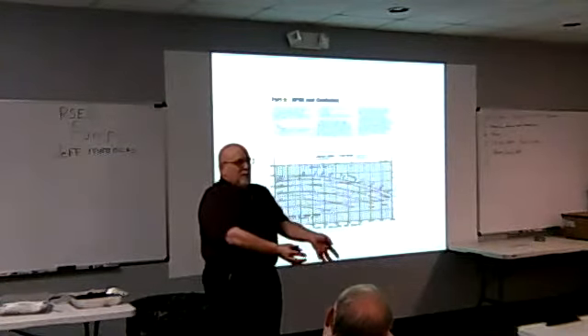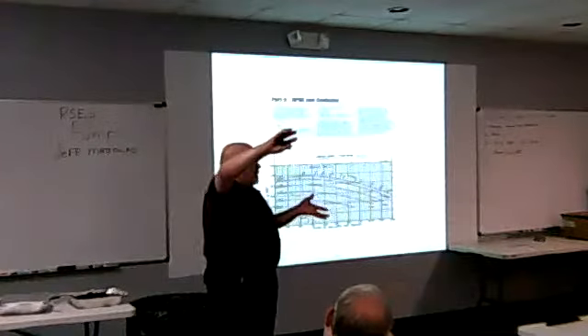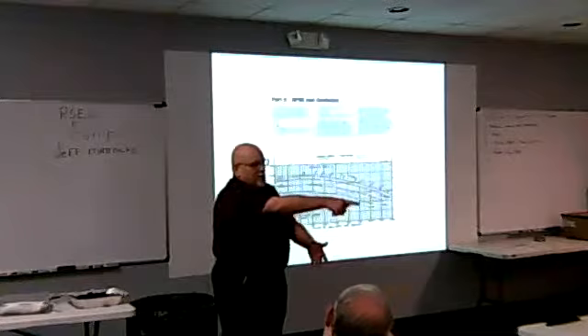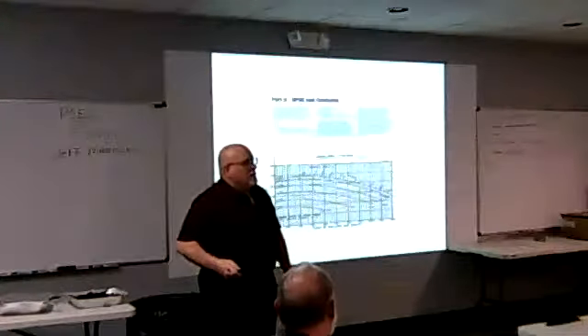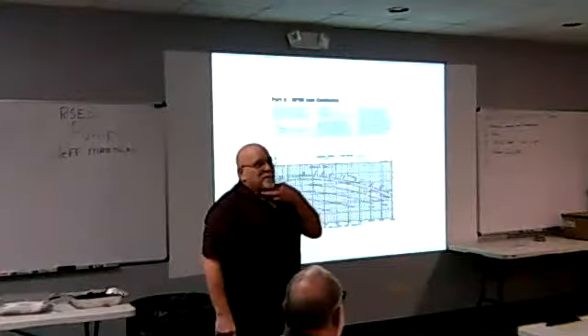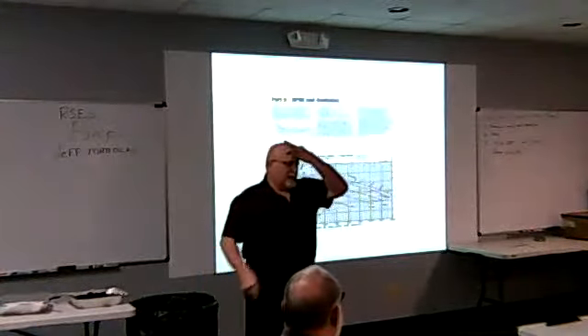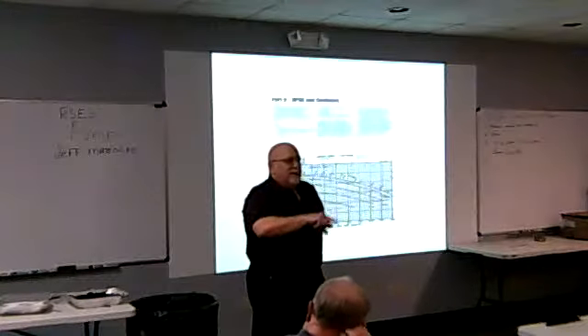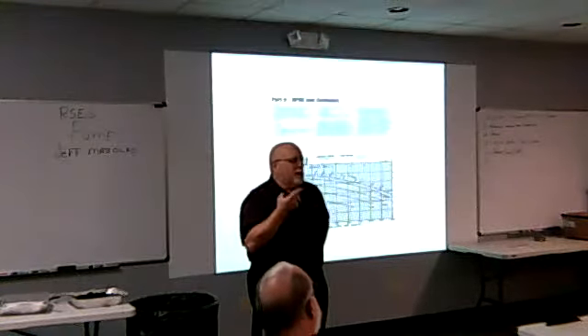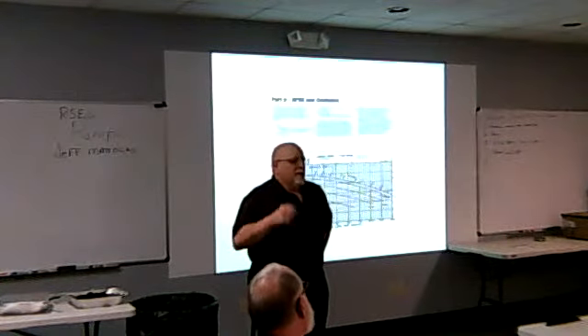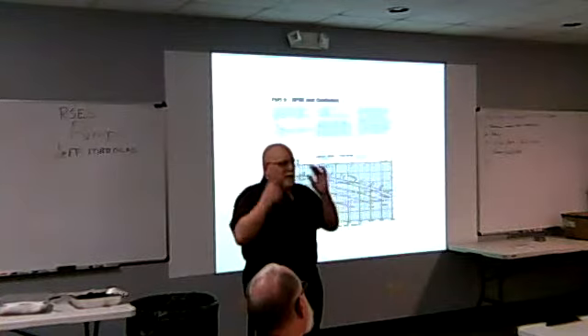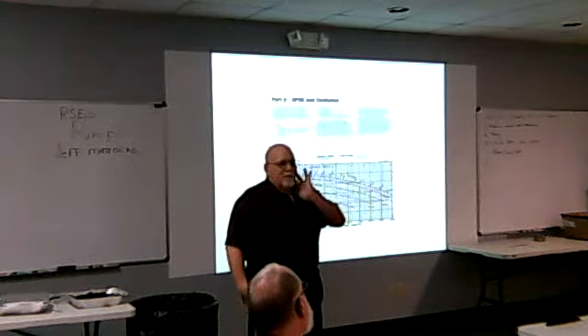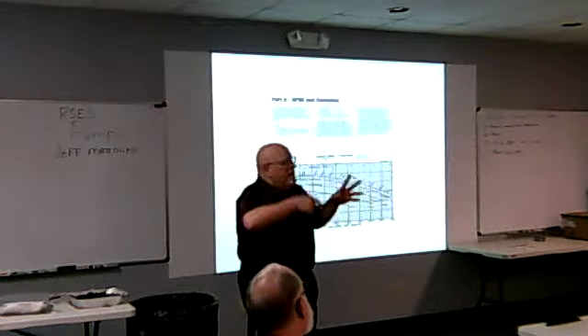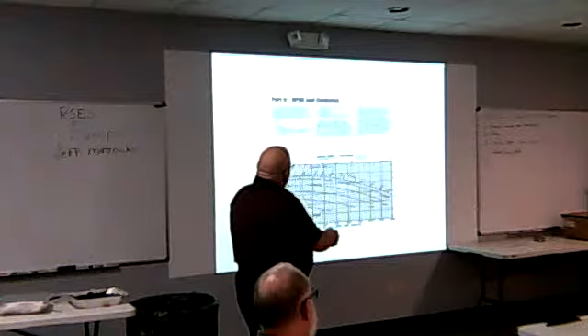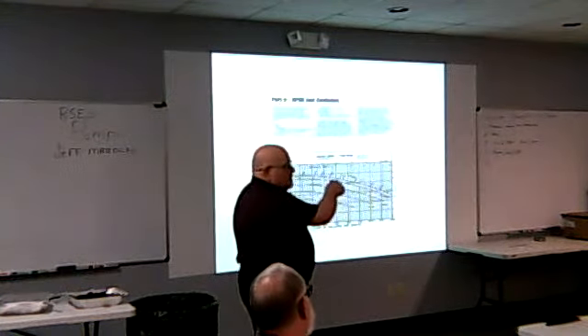And when it boils, there are these little steam bubbles. Now the steam bubbles travel out the vane, hit high pressure, guess what happens to them? They collapse, and they do that. It will destroy an impeller. Tommy knows on our old ship, we had the high pressure turbine, low pressure turbine. I don't know if anybody for the video, we served on the same warship together at different times, but under the main condenser, the two condenser pumps sat there and ran at the same speed all the time. No level controls whatsoever. What happened is they designed these impellers and built them to cavitate. They were built out of titanium or gold or whatever the heck they were made out of, and they run all the time. And as your cavitation goes up, and your NPSH required gets exceeded, your pumping efficiency falls off.